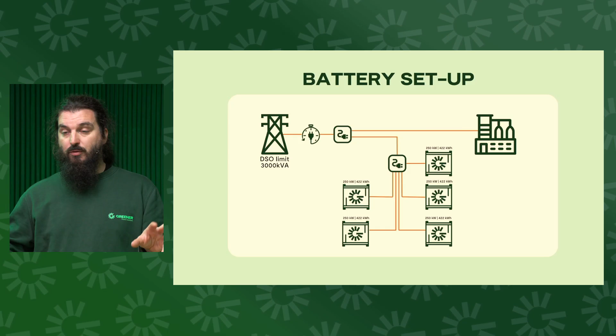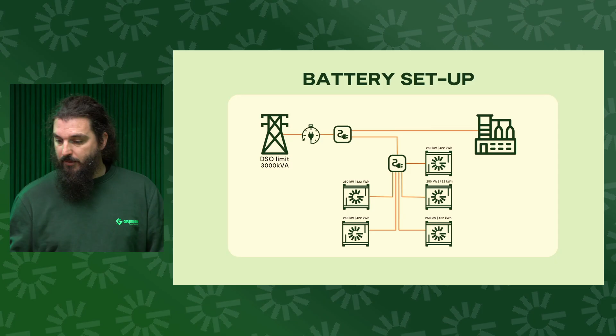What's the beauty of this system? As you can see, there is no diesel here at all, because if the plant has a high demand period of time per day, it also has a low demand period of the day. But the DSO connection is good for its connected value 24/7. So you can use the downtime to charge the batteries, discharge the batteries during the high demand period, and use the very cheap energy coming from the DSO in order to cover the entire peak. And in this manner, we were able to negate all of the diesel generators and have no fuel cost whatsoever. So it was just about timing.